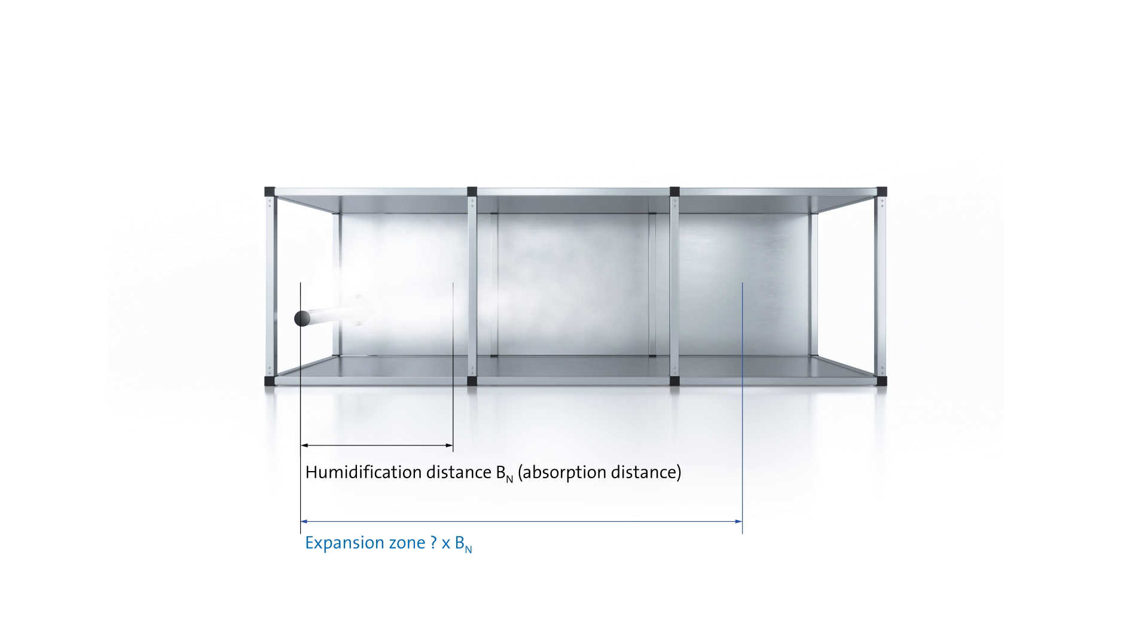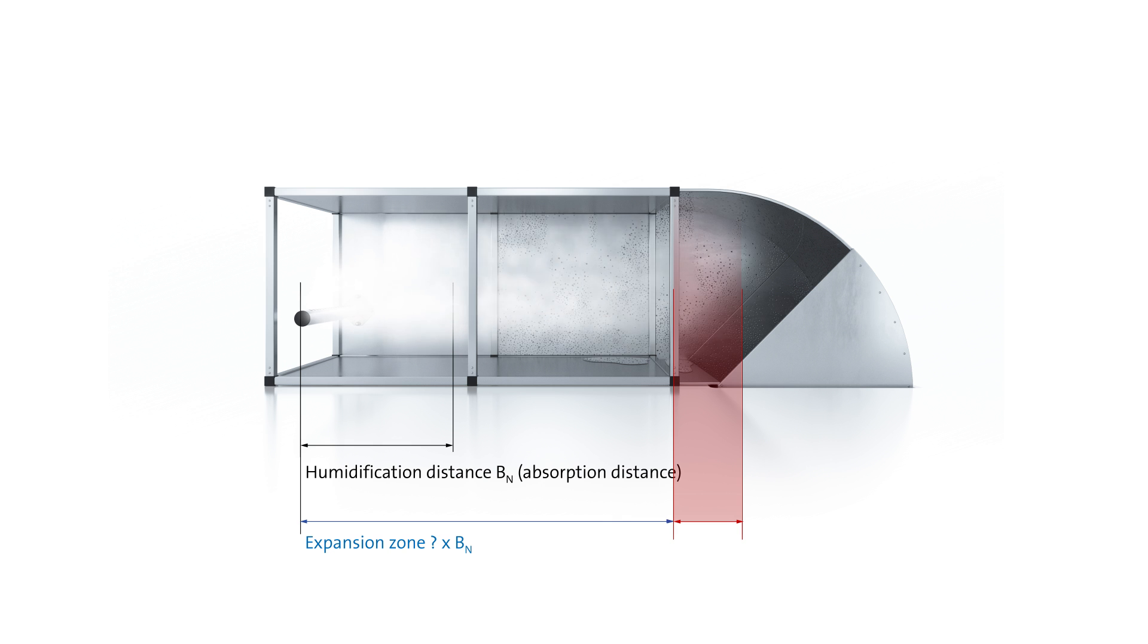If the required distance is not maintained, condensation may be produced with wet spots forming on duct walls, duct branches, on fans, or in filters. This means that the hygiene of the system is no longer ensured and moist hotbeds can form on which bacteria, germs, or mould can thrive. The functioning of the system may also be impaired.